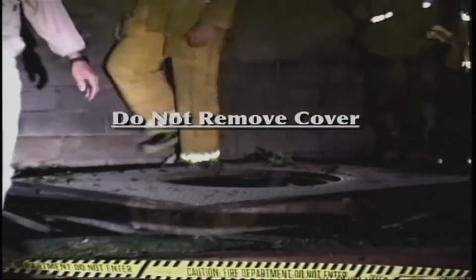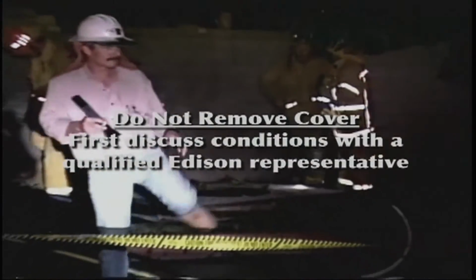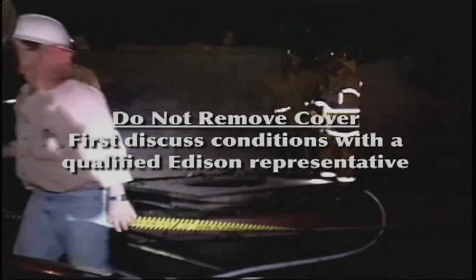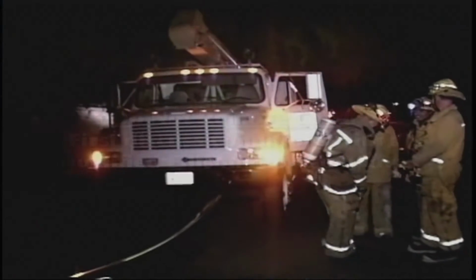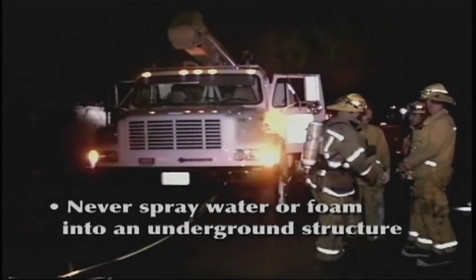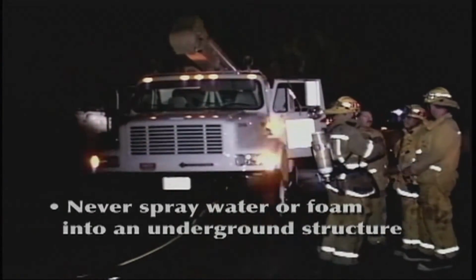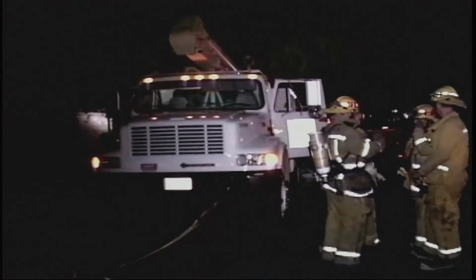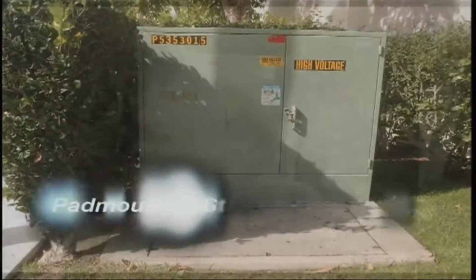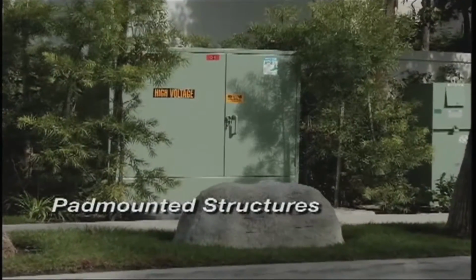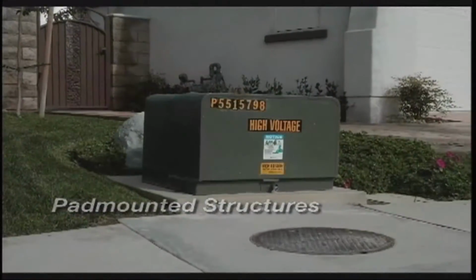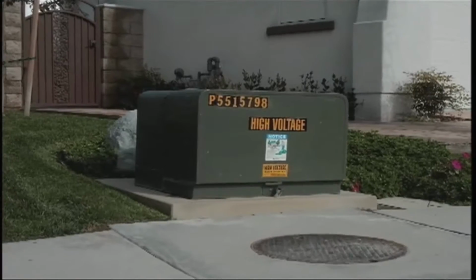If the cover is in place and smoke is coming from the holes in the cover, do not attempt to remove it until the conditions have been thoroughly discussed with a qualified Edison representative. Never spray water or foam into an underground structure, even if a fire is visible, unless the structure has been de-energized.